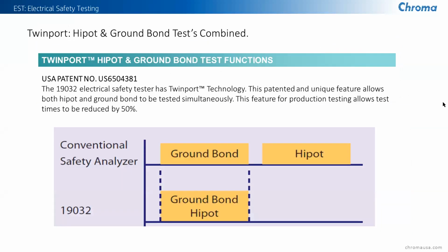Another feature on the 19032 is the ability to combine tests. A typical conventional tester will give you a ground bond test, and then will be followed by a hipot test that are done sequentially, and it adds to the total test time. In our unit, you can combine ground bond and hipot together to create the same test at the same time to cut down on your total test times.